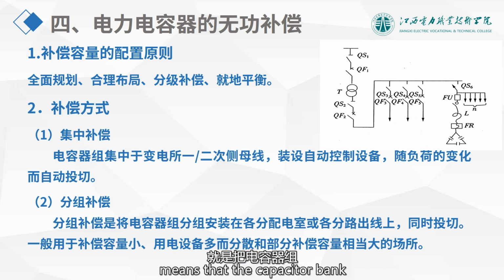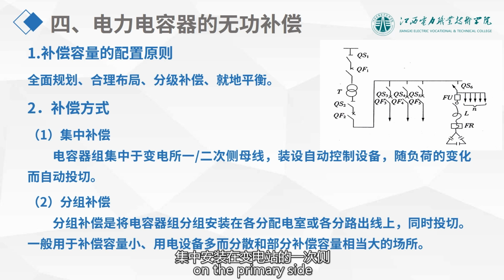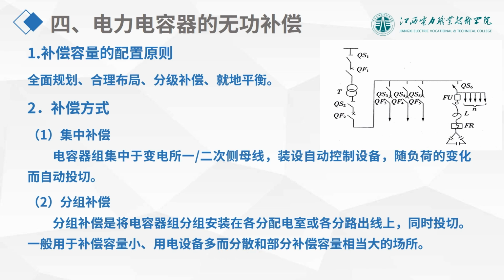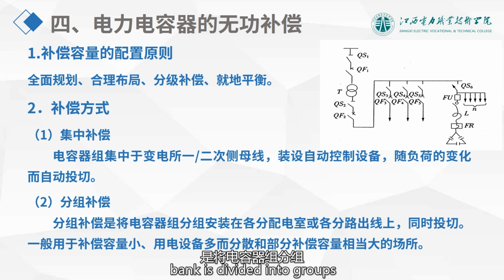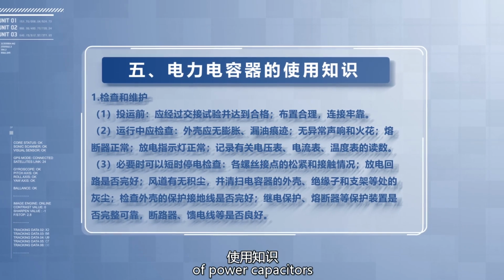Centralized compensation means that the capacitor bank is centrally installed on the primary side or the secondary side bus of the substation. Automatic control equipment is installed to automatically switch the capacitors according to load changes. Group compensation. Group compensation means that the capacitor bank is divided into groups and installed in each distribution room or on each branch line for simultaneous switching. It is generally used in places with small compensation capacity and many scattered electrical devices or places with relatively large partial compensation capacity. Finally, we will introduce the usage knowledge of power capacitors.